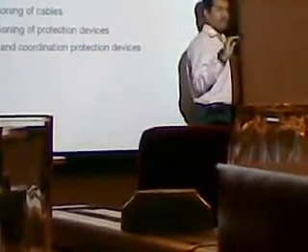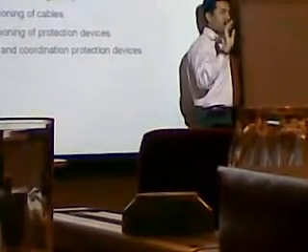I'll show you the discrimination table. You might have seen the ABB discrimination table. In the table, you might find the wording. Suppose here an NS breaker or mini breaker will be there, and here you will have a mini breaker, and here you will have tables. In some places you may see total discrimination, and in some places you may see a value like 5. So this is called partial discrimination.